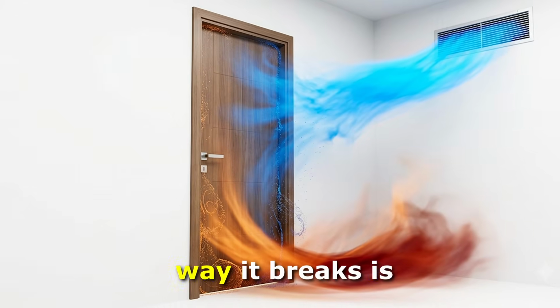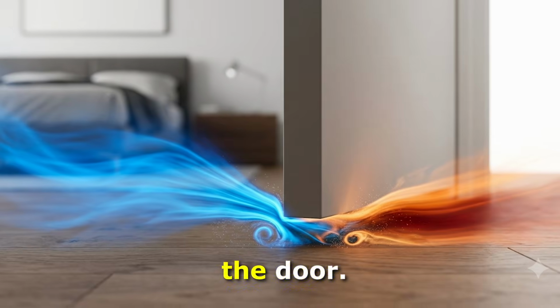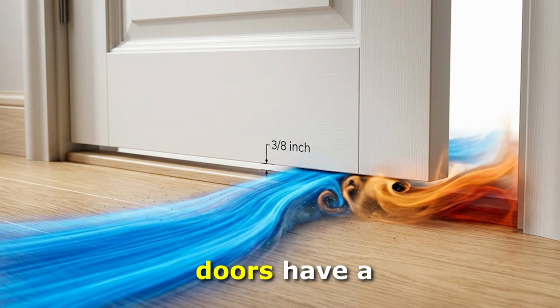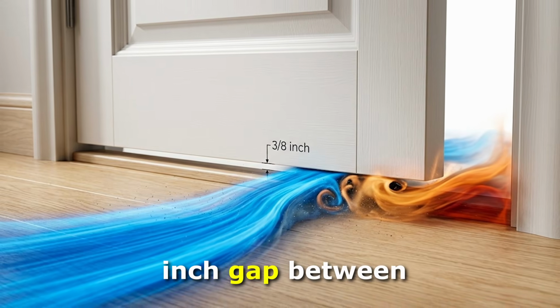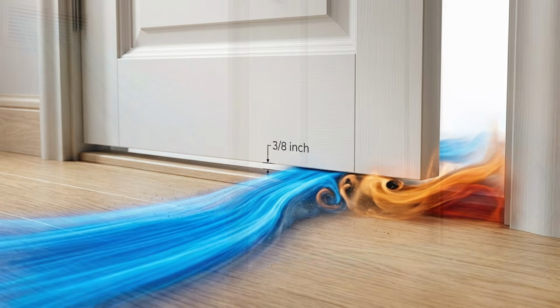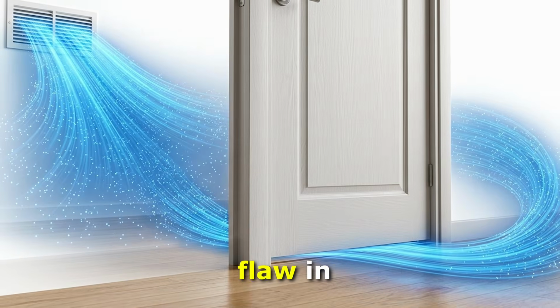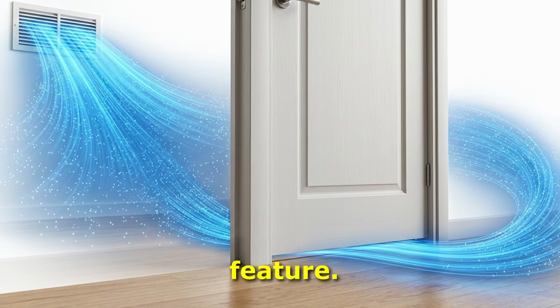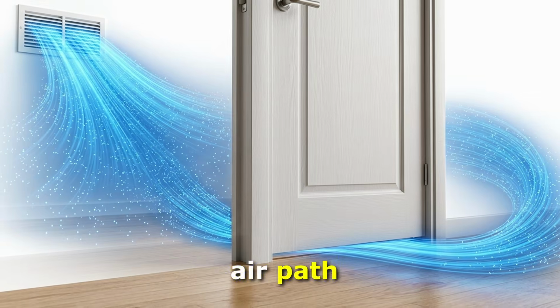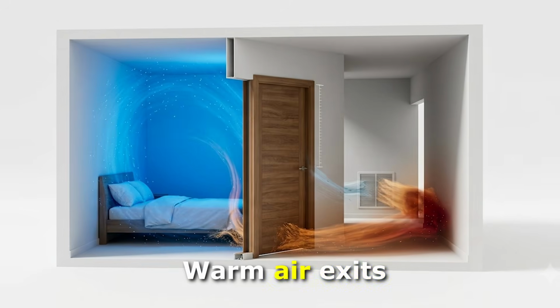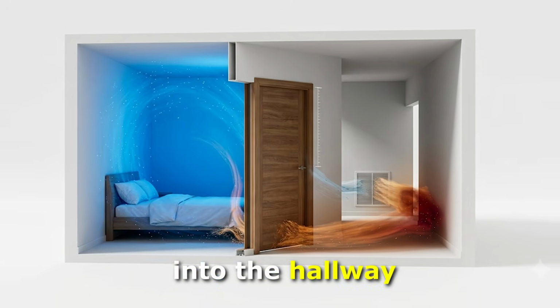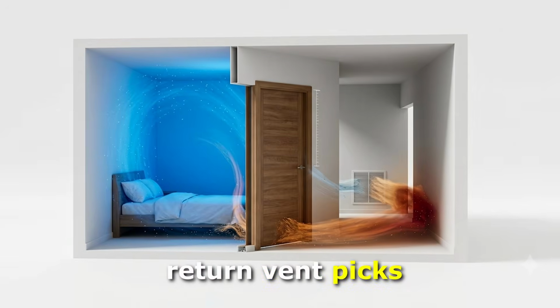The most common way it breaks is through a door, specifically the gap under the door. Most interior doors have a 3/8 inch gap between the door bottom and the floor. That gap is not a flaw in your door. It is a designed feature. It is the return air path for the room. Warm air exits through that gap into the hallway where the central return vent picks it up.